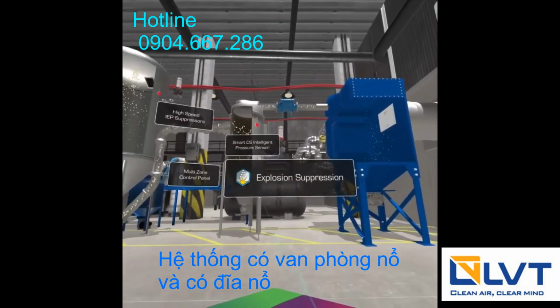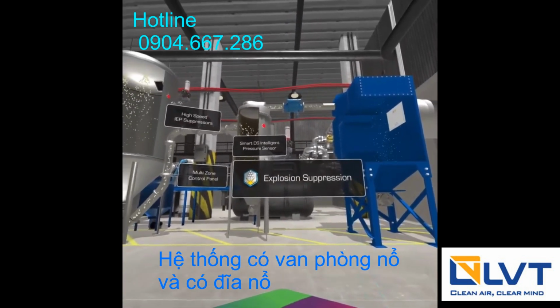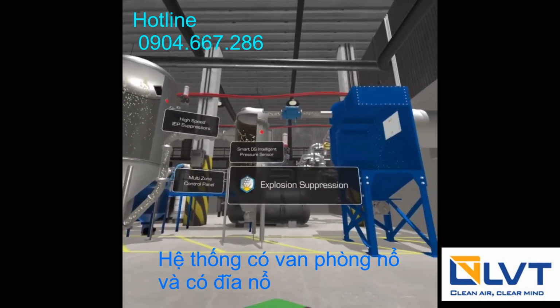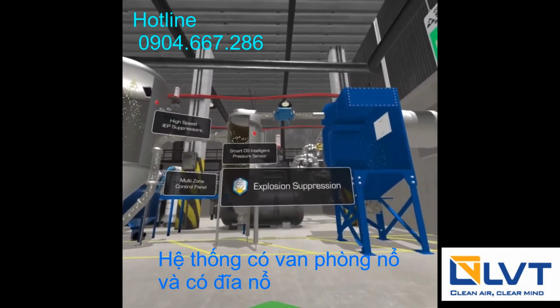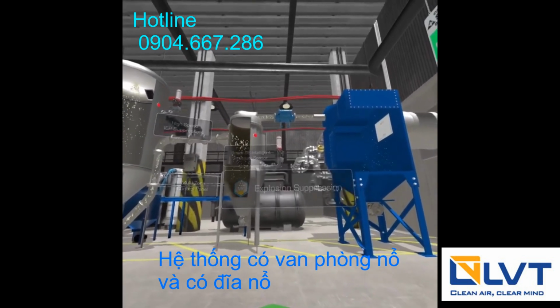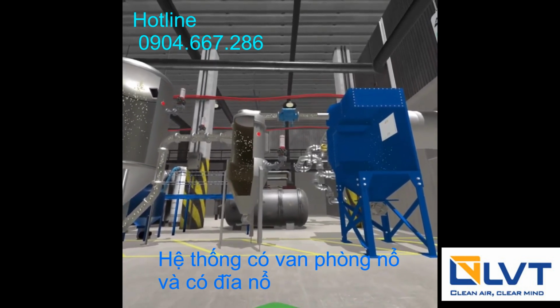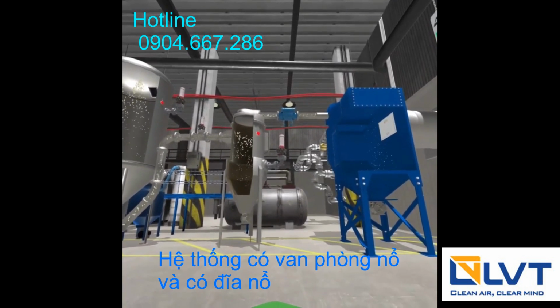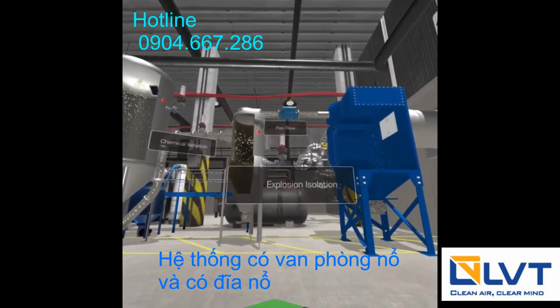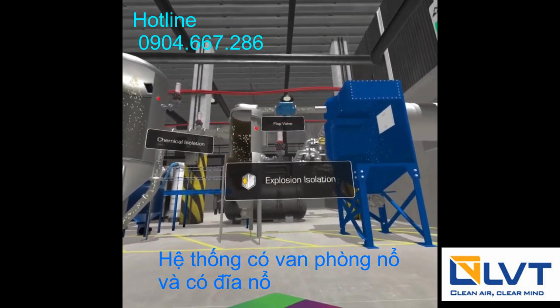Regardless of the type of explosion protection employed, it is important to utilize isolation barriers between vessels. This prevents an explosion from traveling to interconnected vessels and creating a secondary explosion. On our line, we use both a flap valve and chemical isolation.